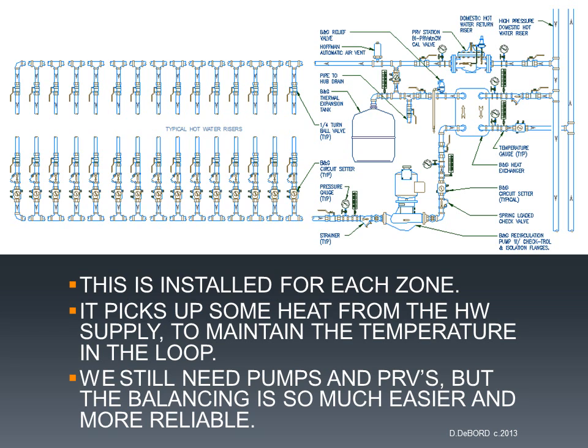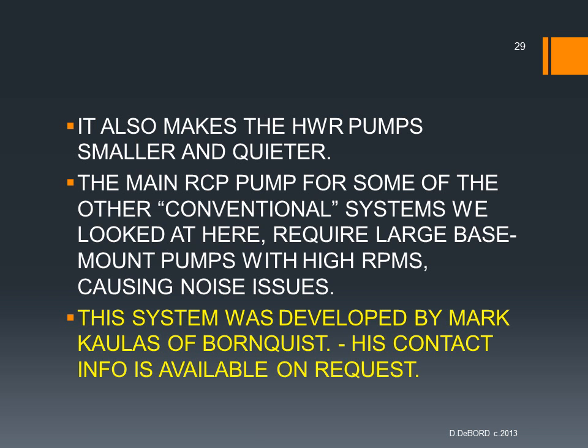We still need pumps and PRVs, but they're very small. And the balancing is so much easier and more reliable because you're only balancing that zone. It's very easy to get back into the main. It also makes the hot water return pipes or pumps smaller and quieter, and that's really important. The main RCP pump for some of the other conventional systems that we talked about are large base mounted pumps. High RPMs cause a lot of noise.